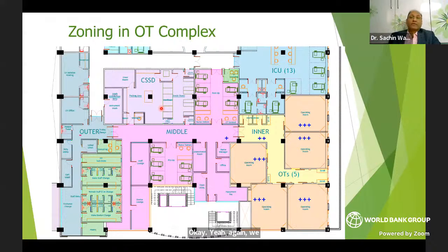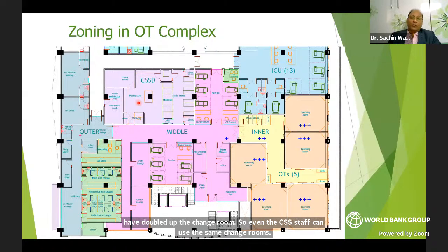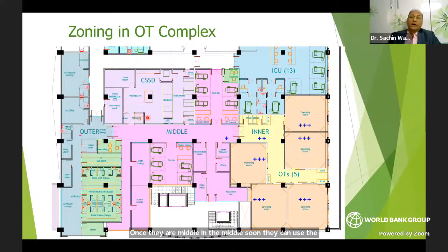Because the CSSD was very close, we doubled up the change rooms so even the CSSD staff can use the same change rooms. Once in the middle zone, they can use the ante room to enter the packing room, and from packing through the ante room again go to the sterile store, and the same way back. This is how the pressures in the CSSD are maintained, from a very high sterile area to the clean area to the dirty area, which has negative pressure.